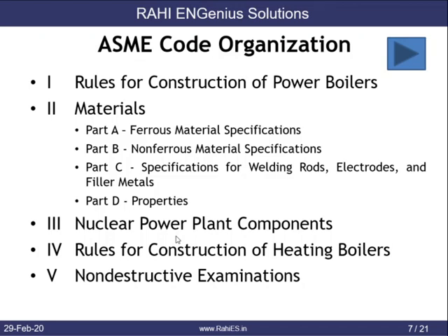The ASME Boiler and Pressure Vessel Code is organized into 12 sections. Section 1 contains rules for construction of power boilers. Section 2 covers materials and is divided into four parts: Part A for ferrous material specifications, Part B for non-ferrous material specifications, Part C for specifications of welding rods, electrodes, and filler metals for both ferrous and non-ferrous materials, and Part D for the properties of all materials listed in Parts A, B, and C. Section 3 covers nuclear power plant component requirements, Section 4 covers rules for construction of heating boilers, and Section 5 covers NDE examinations.